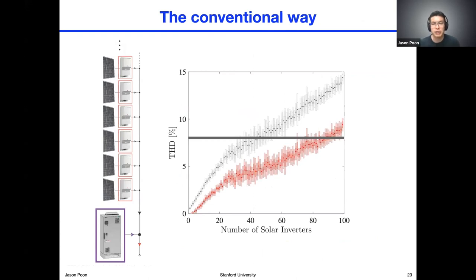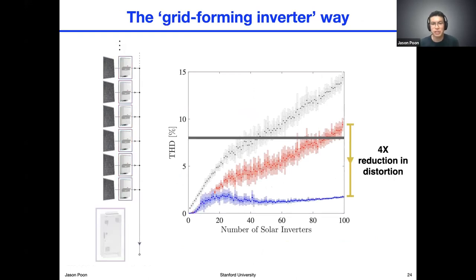We can see in this cartoon that if we pick the phase shifts of these various waveforms in this particular way, we can actually dramatically reduce the magnitude of distortion in the aggregate waveform. We formulated it as an optimization problem with different cost functions to explore. Importantly, we could formulate this as a decentralized optimization problem. Evaluating how this technique compares to the conventional way — we can achieve a dramatic reduction in distortion even compared to the case of using an active power filter — up to 4x reduction in THD.